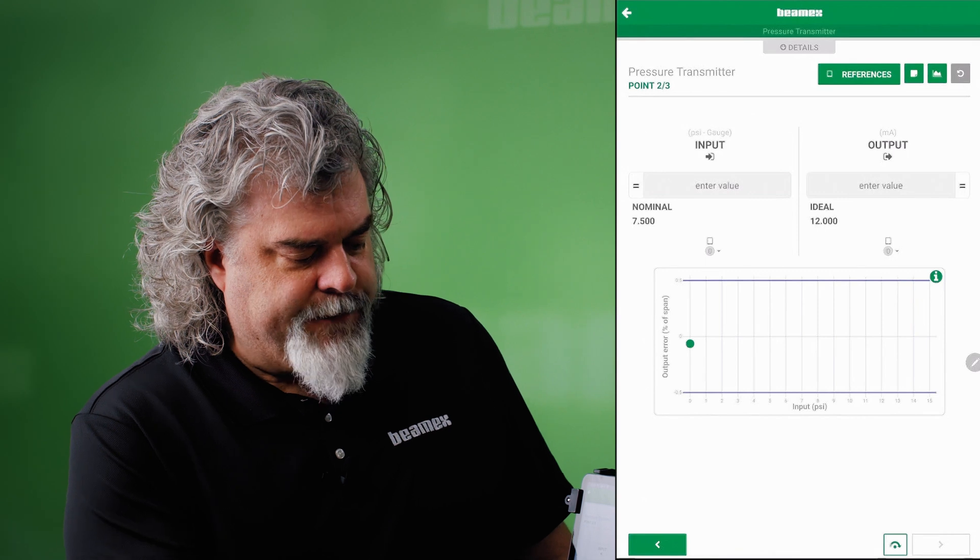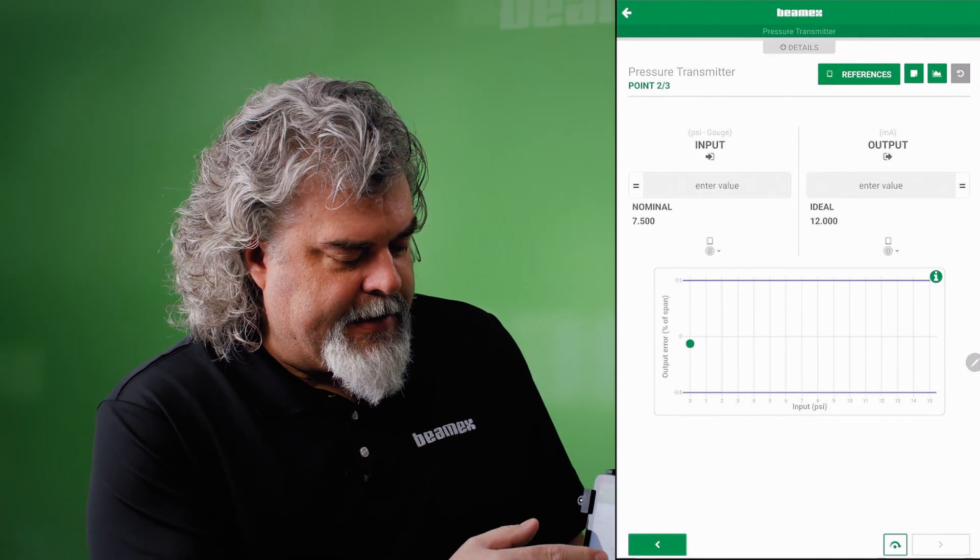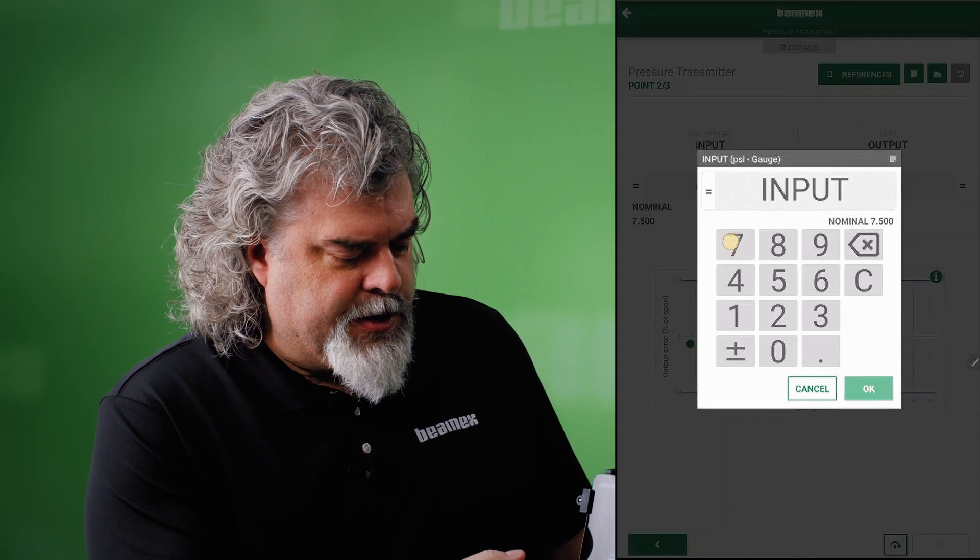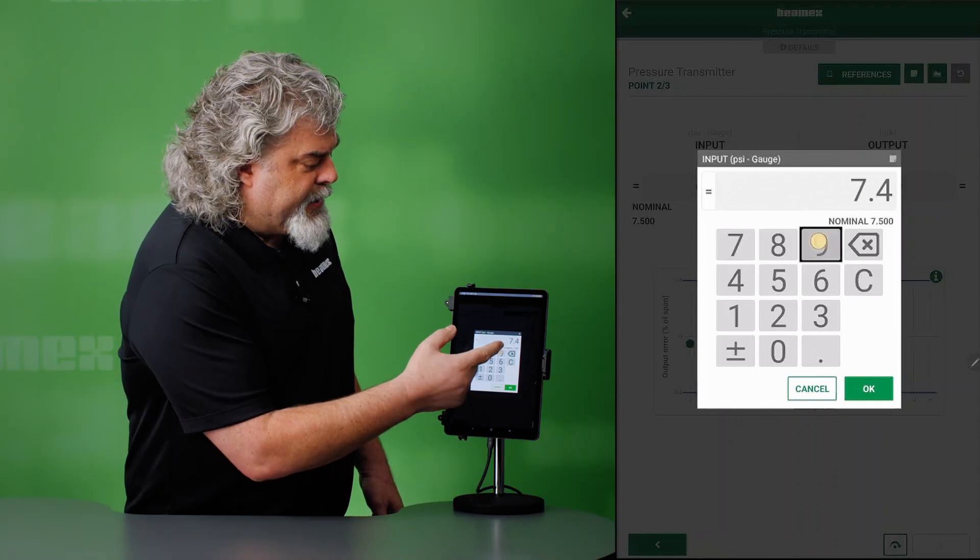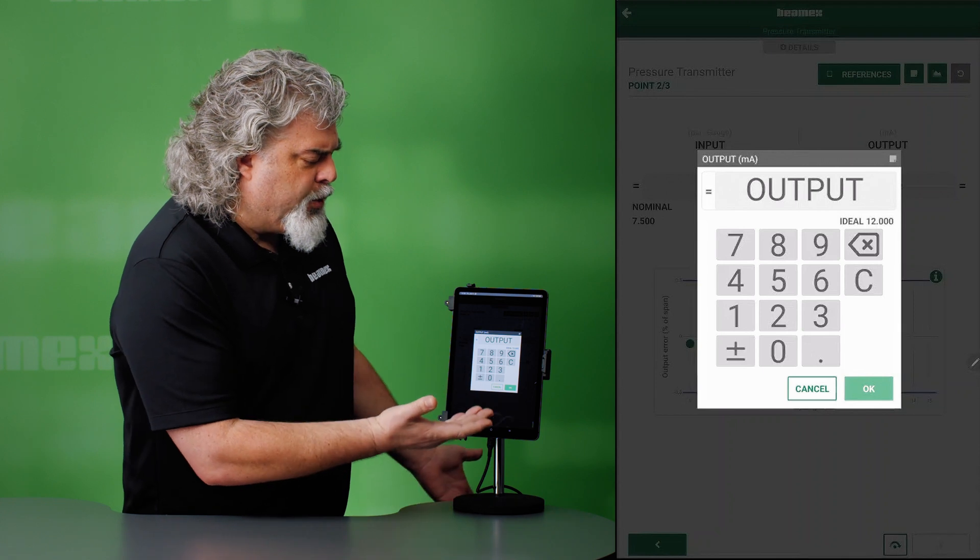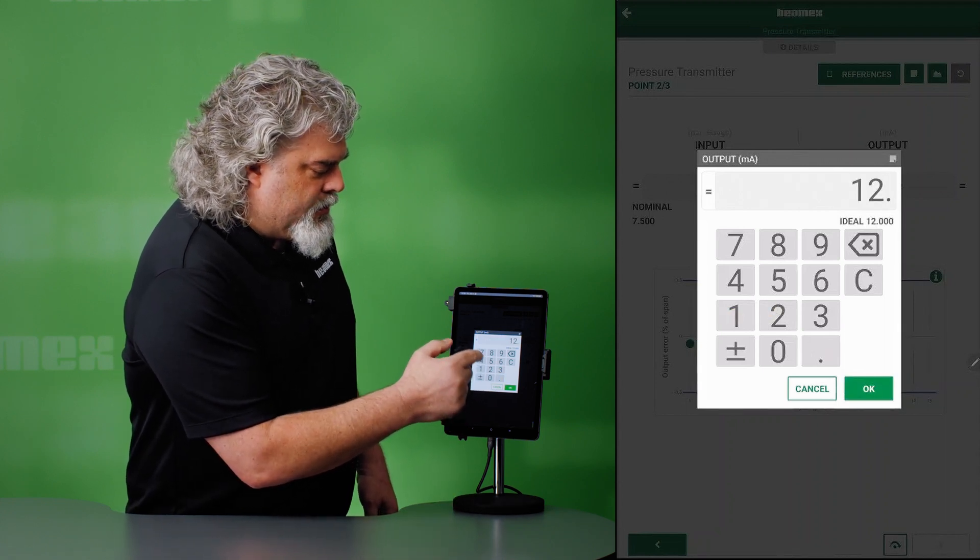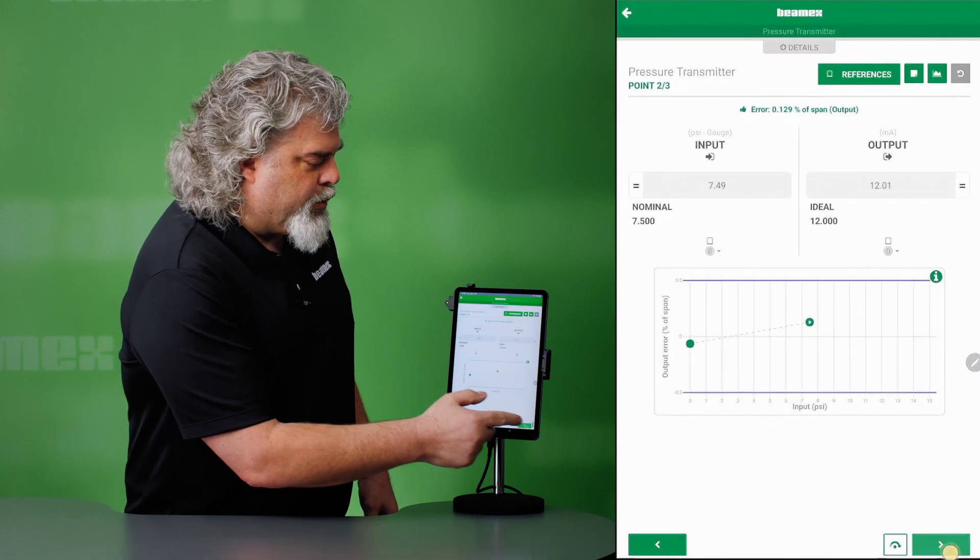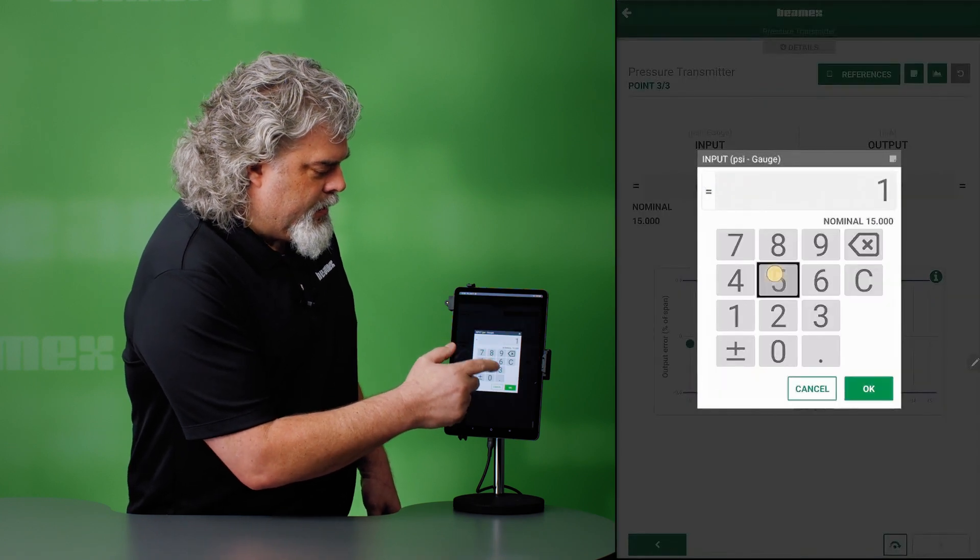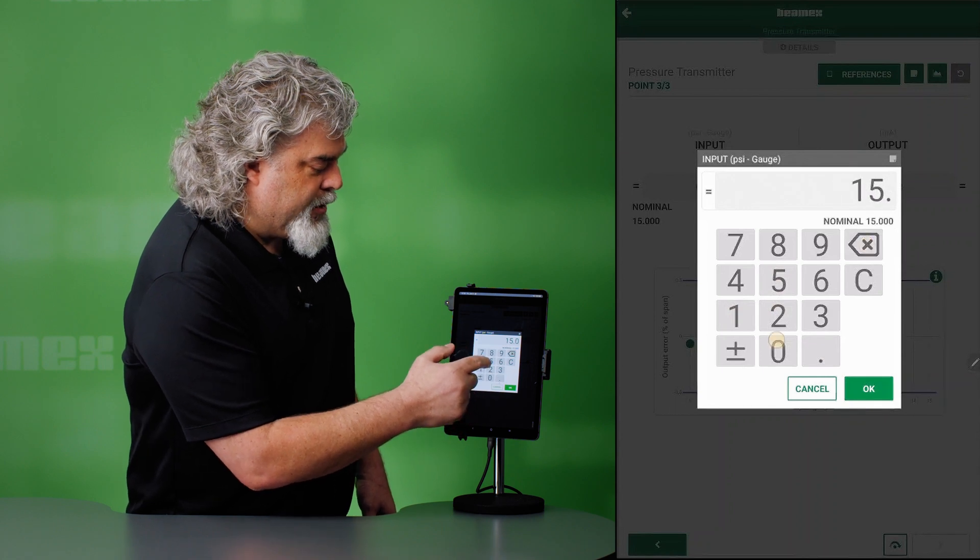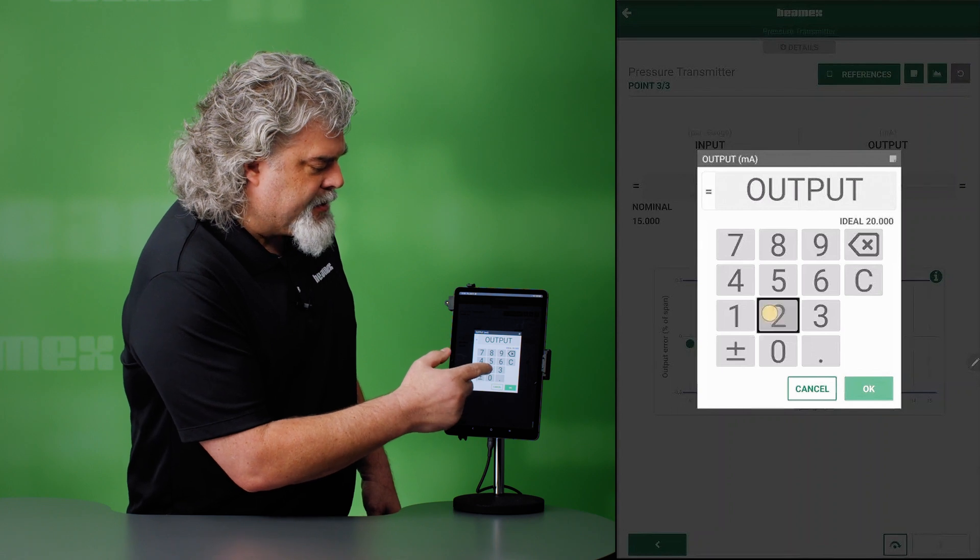Next. This is my 50% point. Nominal is 7.5, and that's ideal. With pressure, it's difficult to get it exact unless you're using a smart positioner or a smart pressure regulator. Let me go 7.49. We say that's the actual pressure going in. We're expecting 12 milliamps out. And 12.01 is what I am reading on this one. Next point. This will be our high point or 100%. 15.02. Hit OK. Output. We're expecting 20 milliamps.